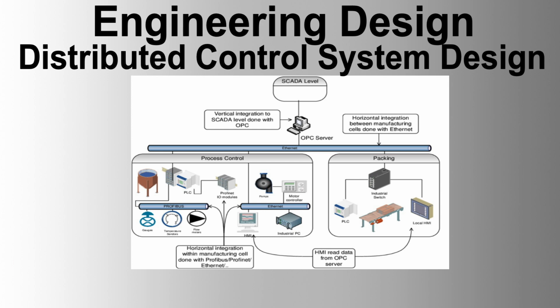2. Redundancy and fault tolerance. Redundant controllers, power supplies, communication buses, and I/O modules must be provided to ensure system reliability. Redundant components must automatically take over in case of primary component failure without operator intervention. The system must be designed to continue operation without degradation in performance upon single component failure.